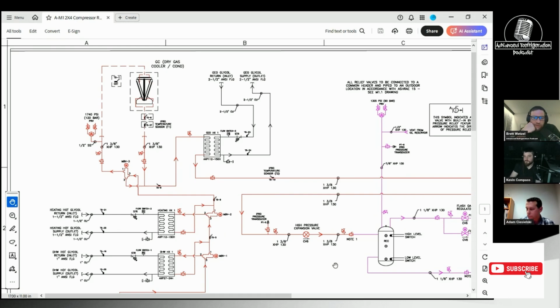Does that system have to be 90 bar in order to accomplish that, or is that something you found you can do with a lower pressure system? You can do it with a lower pressure, but it just doesn't work as well because, like I said, it's limited to 650. It doesn't get very high from a defrost temperature perspective, whereas with a 90 bar system, you can raise that up to a 55 degree saturated temperature, which would be above 650. So to get the full benefit out of it, you really need a 90 bar system.